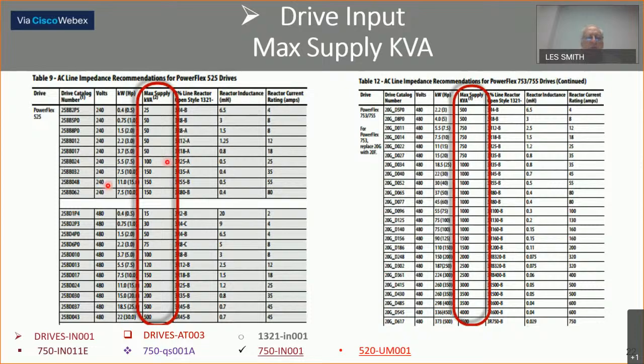On all of these, see where this is grayed out? This guy doesn't have an inductor in it. And I think there may be an inductor on the very largest size, but you can see how it affects how big the transformer can be without the influence of damage. So that table will be for all the drives specifically, and you should check on installation what your power distribution is. That would aid you in a decision to put reactors in or not.